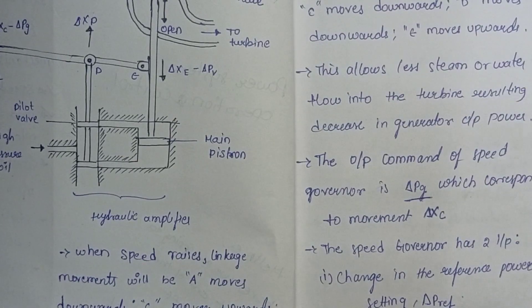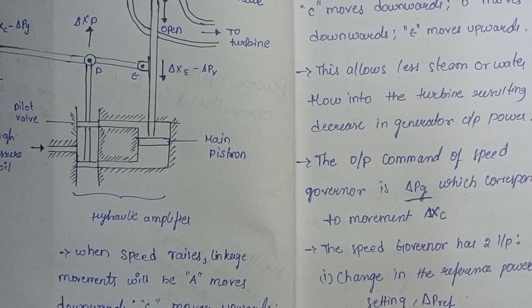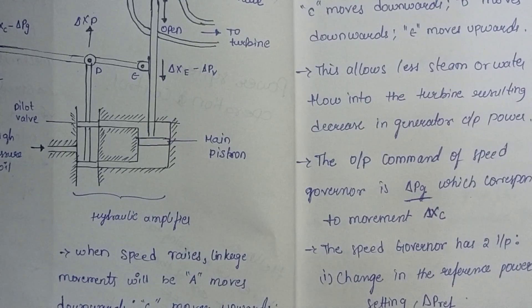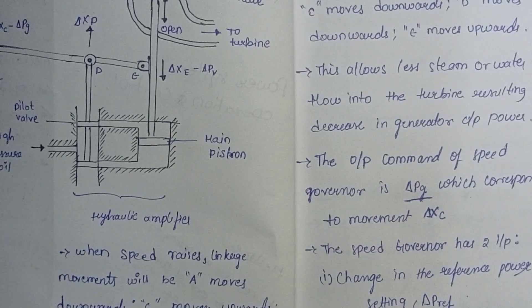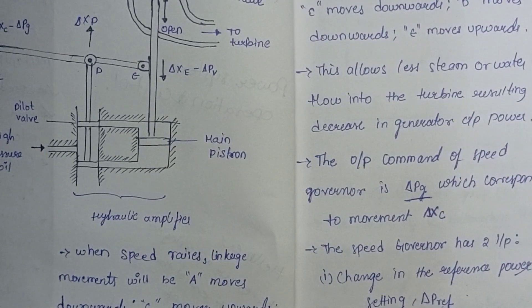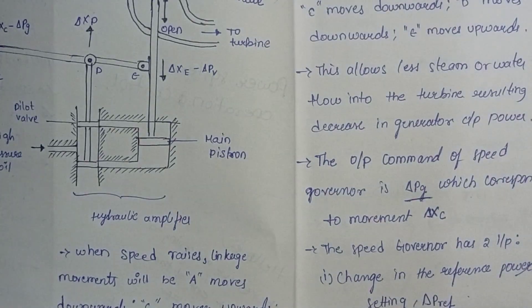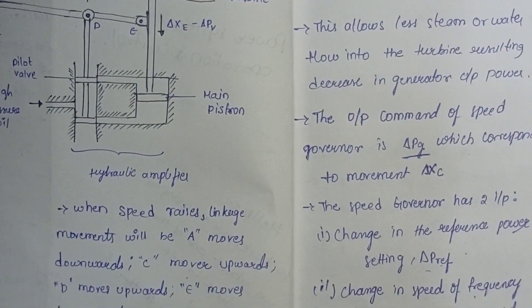The first input to the speed governor is the reference power setting — that is delta P reference. The second input is the change in speed or frequency of the generator — that is delta F, as measured by the movement of delta XB. So these are the two inputs of the speed governor: reference power setting and change in frequency.